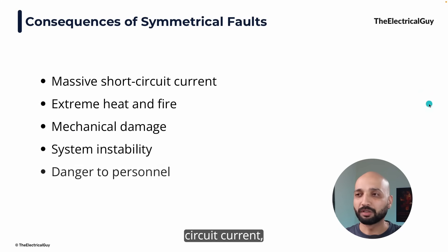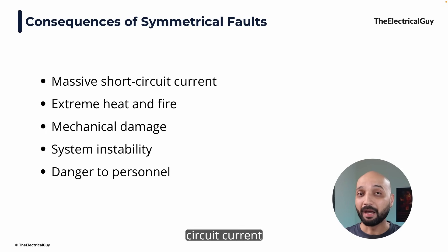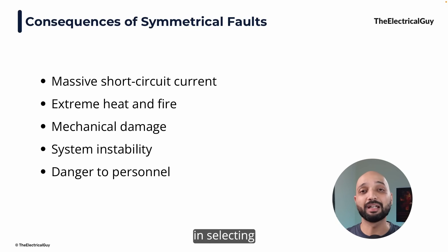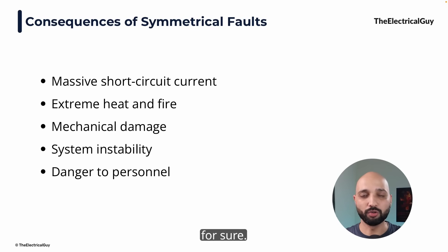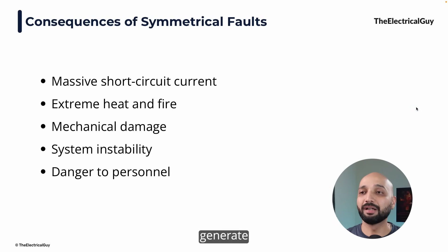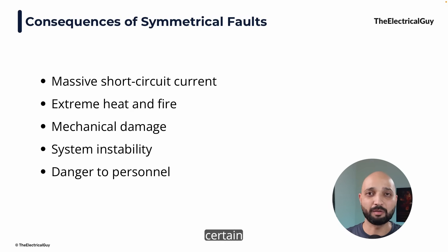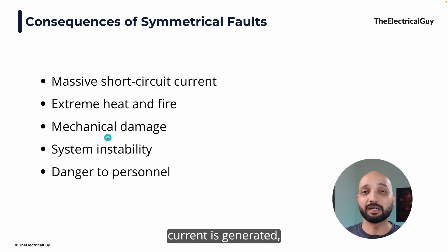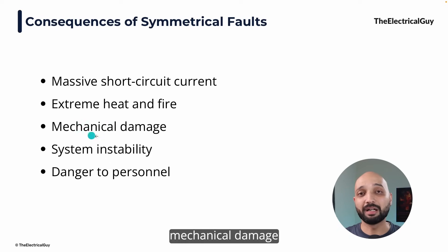The consequences of symmetrical fault are serious. The massive short circuit current it generates is a major contributing factor in selecting the short circuit capabilities of the circuit breaker — you cannot ignore it. Since a lot of short circuit current is generated, it will generate a lot of heat, and if this fault is not handled within a certain amount of time, it may result in fire as well. The huge short circuit current also generates electromagnetic forces that can create mechanical damage to equipment.